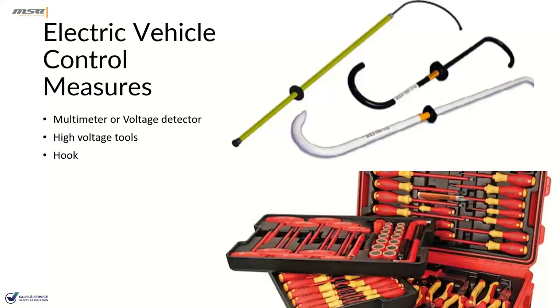Moving on to the multimeter or voltage detector—another essential piece of equipment used in vehicle shutdown and the test process. This device checks the absence of voltage at a suitable test point. Like the high voltage insulated gloves, there are tests you need to complete every time this device is used to confirm it works correctly. We also want to make sure we're using high voltage tools rated at 1,000 volts when working on these high voltage components; these tools are essential for protecting staff.